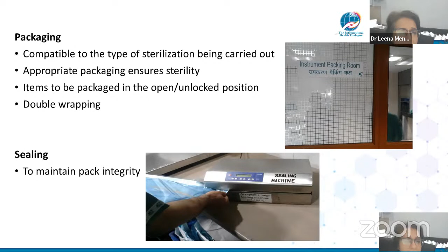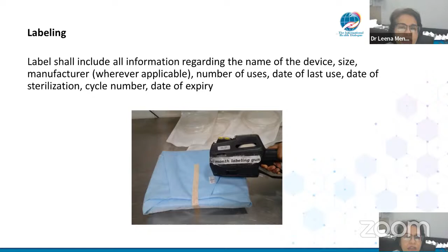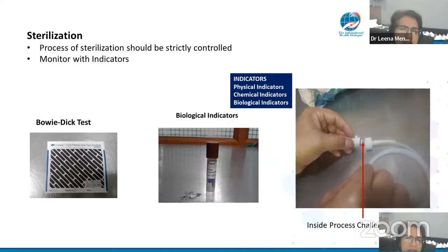The labeling conforming to the sterilization, including all things with the help of the gun, can be used, like the name of the sterilizer, the size, the number of uses, the date of last use, the date of sterilization, the cycle number, and the date of expiry related to the sterilization. So this is a sterilization specific label that we are right now talking about. The process needs to be very strictly controlled, very, very important, with the help of indicators. So the Bowie test can be made use of, biological indicators, which we are using in every pack. And again, inside the process challenge device, various indicators can be made use of.